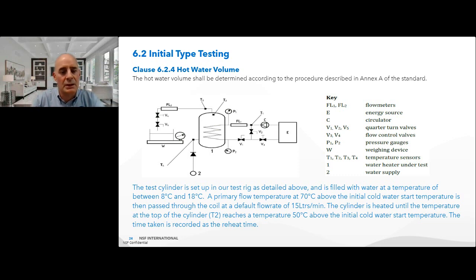70 degrees above the initial is then passed through the coil at a default flow rate of 15 litres a minute. This default flow rate can be changed if the manufacturer specifies a different flow rate, then that can be set for this test. But that flow rate will then need to be marked on the label to show that those heat up times have been obtained using that specified flow rate. The cylinder is heated until the temperature at the top of the cylinder, capital T2, reaches a temperature of 50 degrees above the initial cold water start temperature. The time taken is recorded as the reheat time.